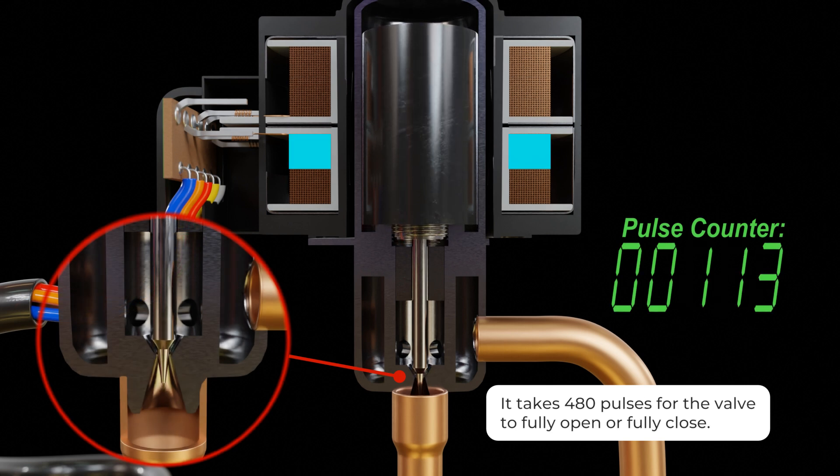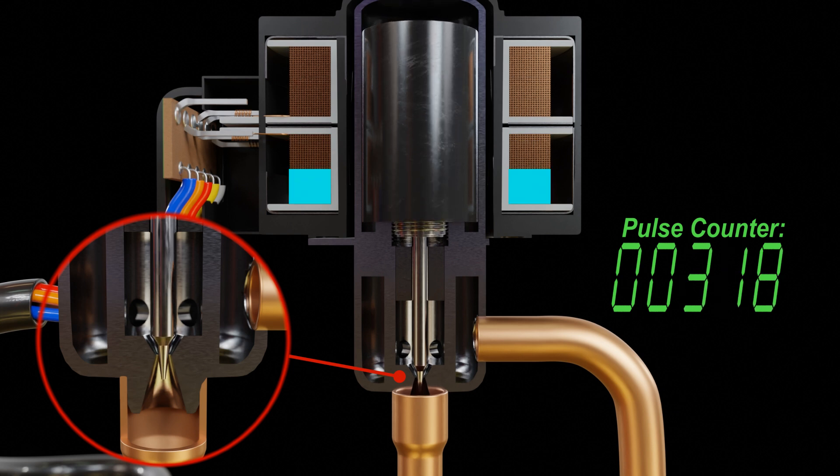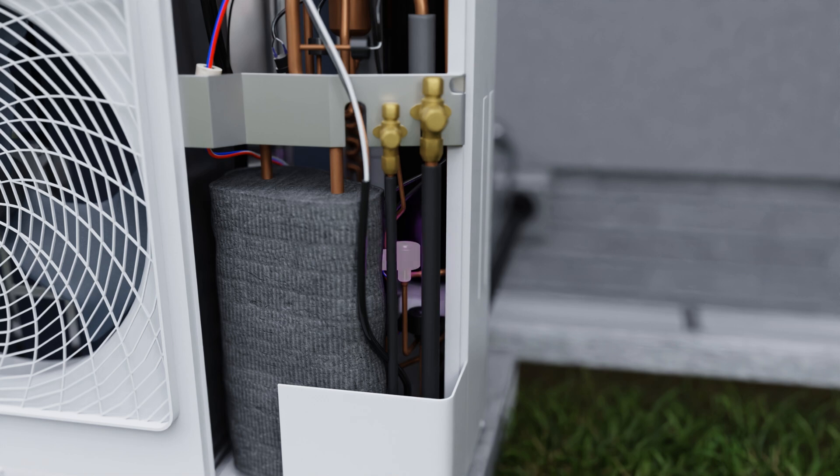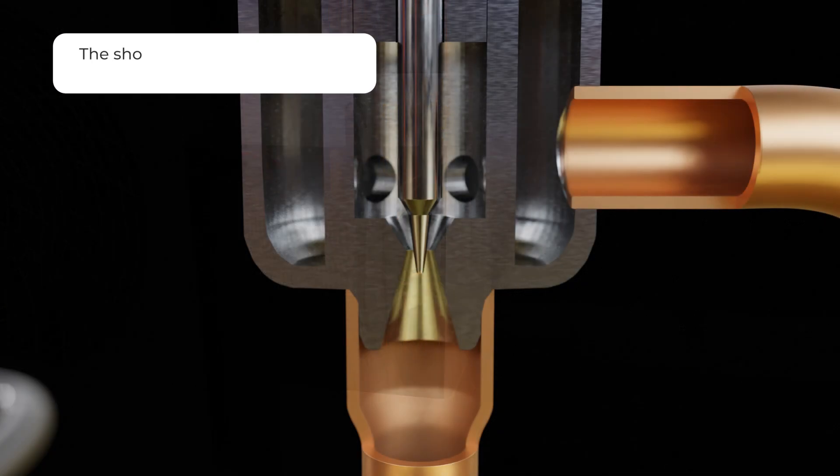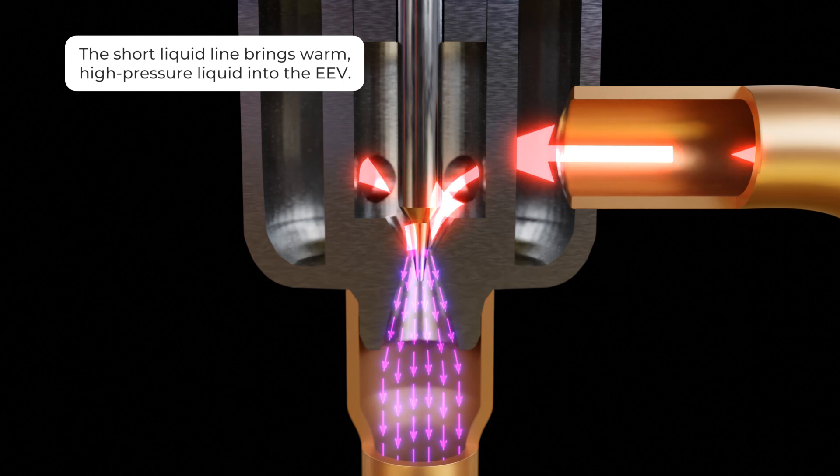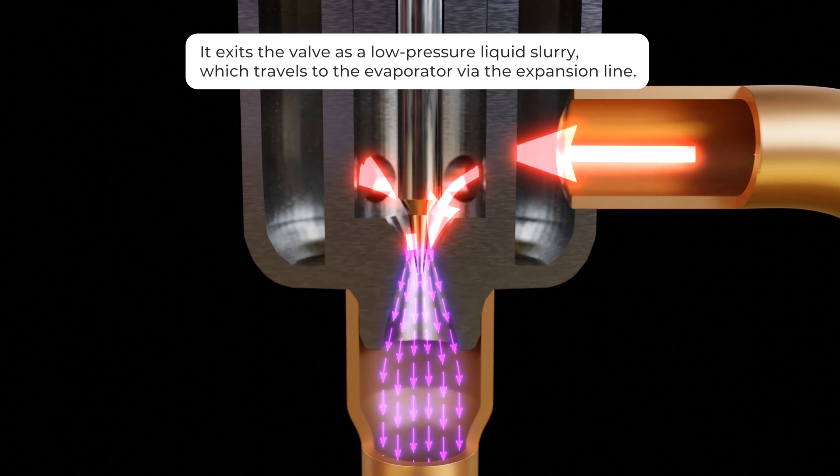It takes 480 pulses for the valve to fully open or fully close. You'll often see these at the outdoor unit in mini splits and also VRF equipment. The short liquid line brings warm high pressure liquid into the EEV and it exits the valve as a low pressure liquid slurry which travels to the evaporator via the expansion line.